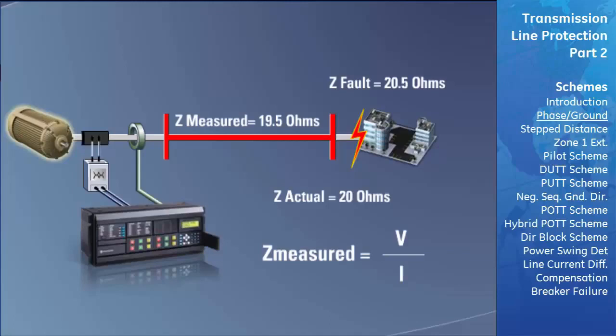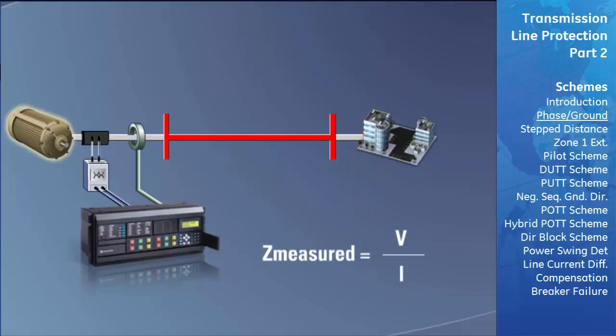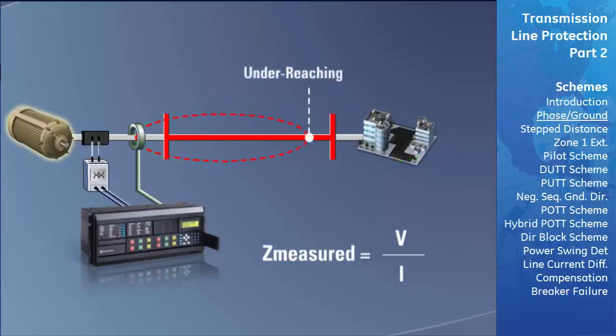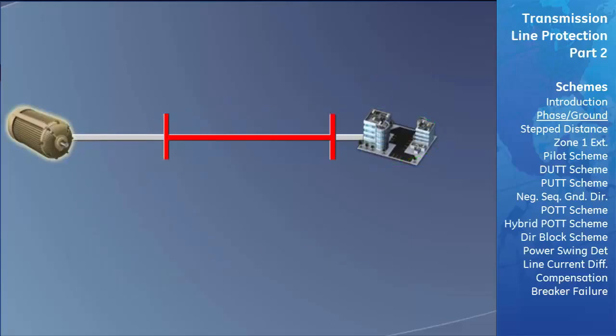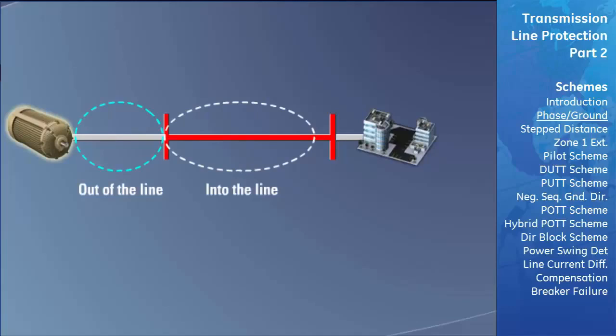Because of these inaccuracies, distance zones of protection are not set to stop right at the boundary of a transmission line. Distance relays use multiple zones, with some set short to protect only part of a line, and others set longer to protect the entire length plus some of the next adjacent line. Zones set to cover only part of the line are said to be underreaching, while zones set to cover more than that relay's line are said to be overreaching. Zones can also be programmed to protect in either the forward or reverse direction.